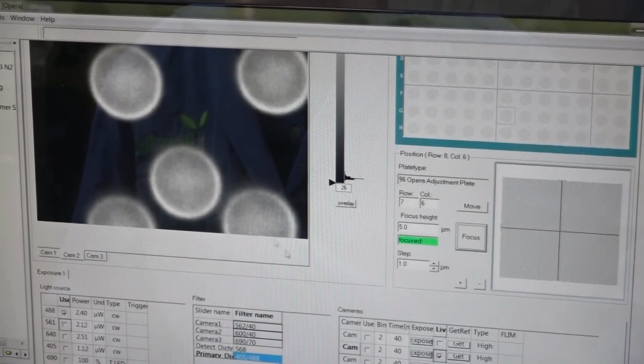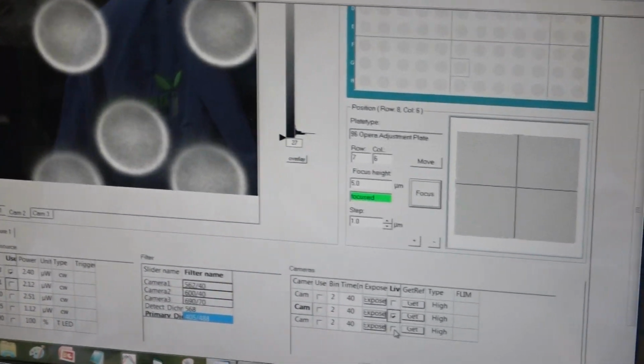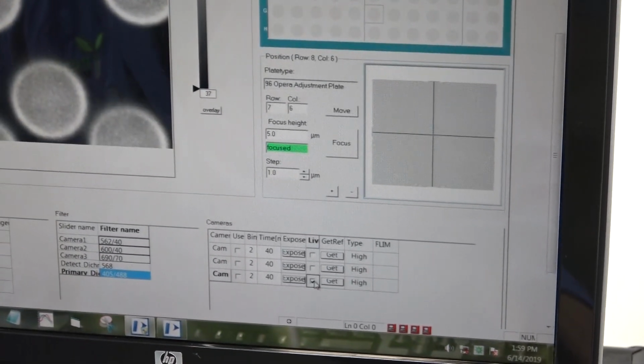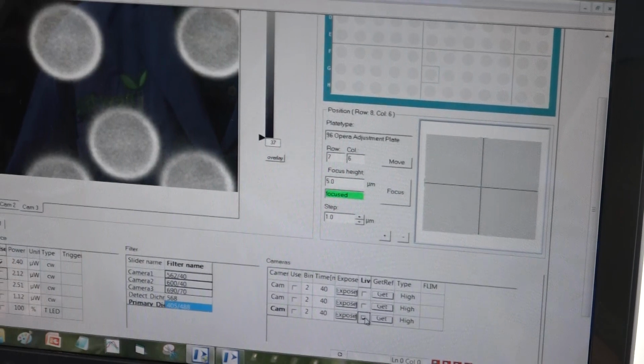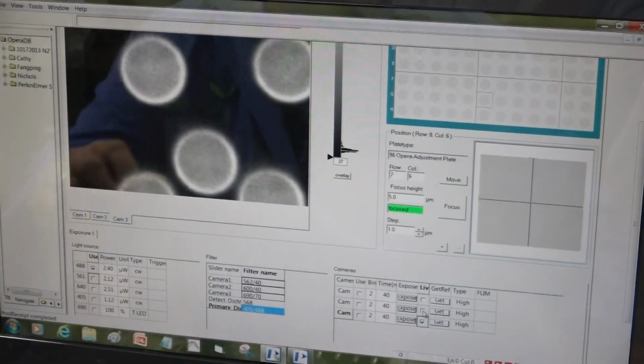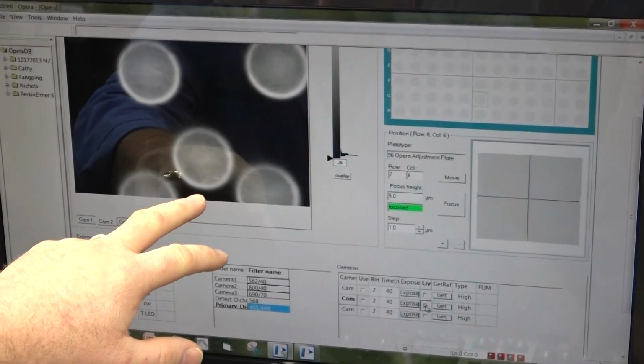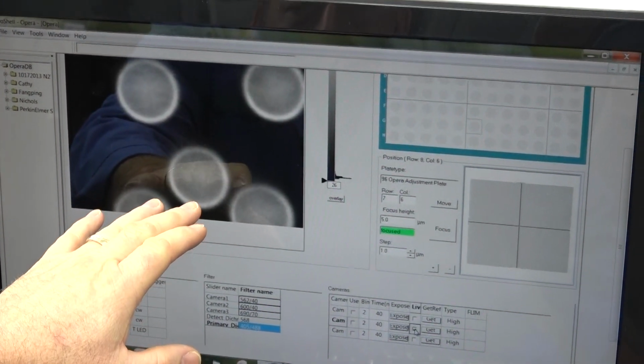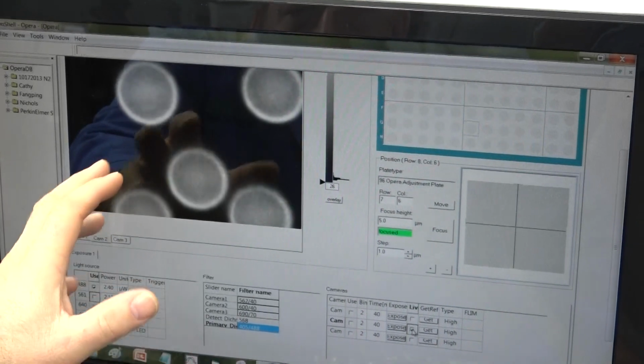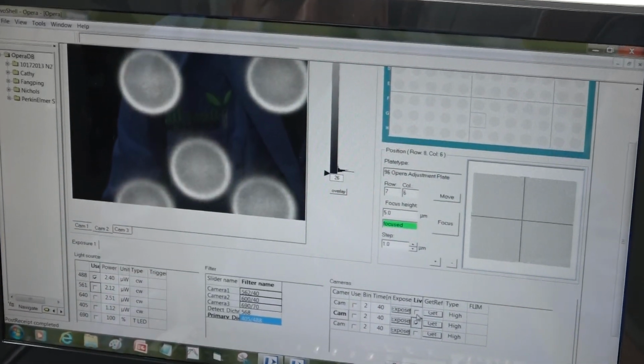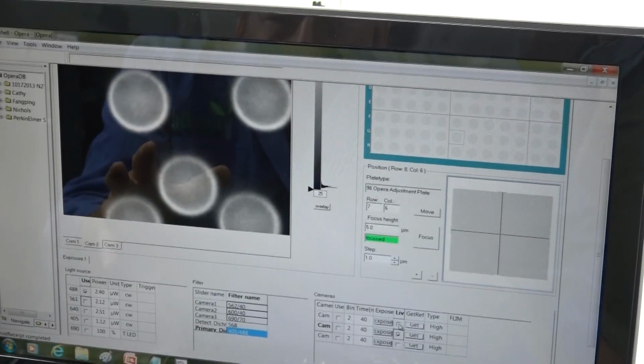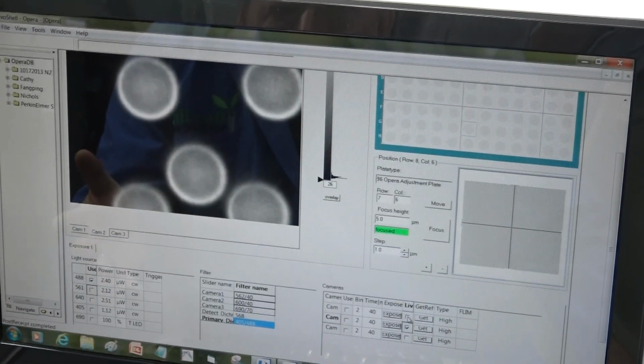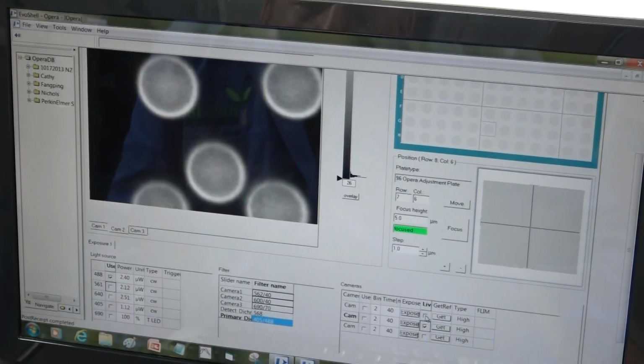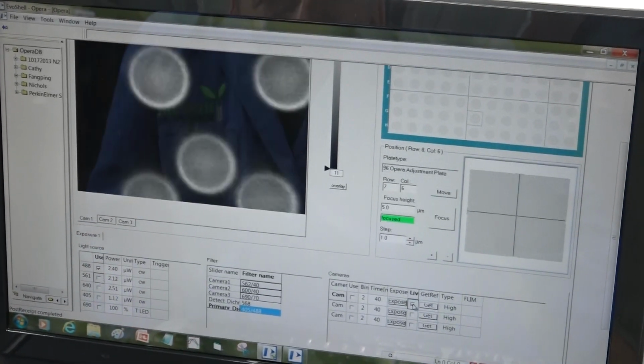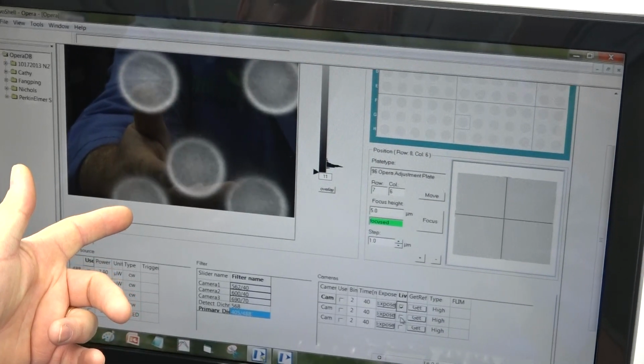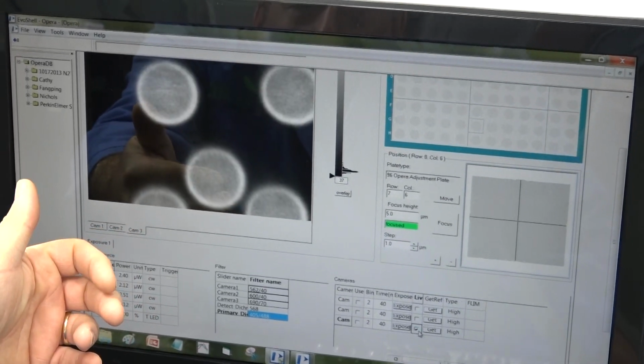But this is camera 2. And we're going to move through the cameras and we're going to look at camera 3 down here. And you can notice that it's the same image, but it's shifted just a little bit. You can see how this is actually shifted down from camera 2. And that means the cameras aren't quite aligned. And again, for me to take the time to do it until it's actually set up, it's not worth it, because once it's set up and it's ready to be used in the lab setting, then you can set all the lasers, you can set all the cameras and get everything just perfect. But this is also camera 1 now. So we got camera 1, camera 2, and camera 3.